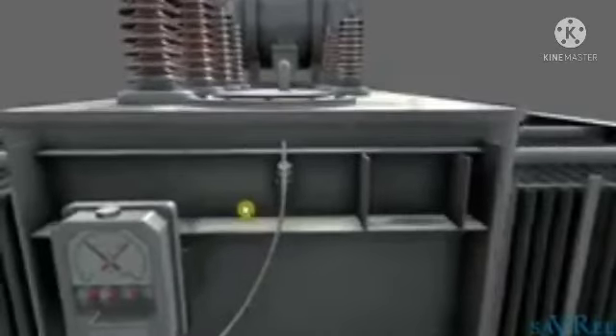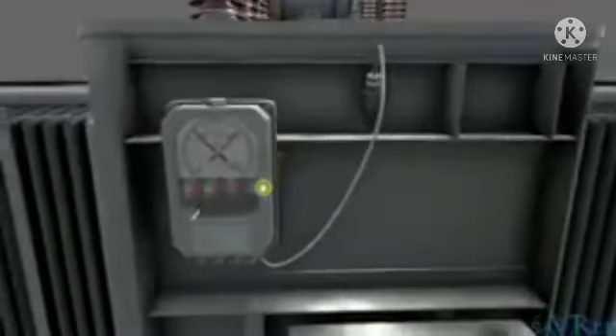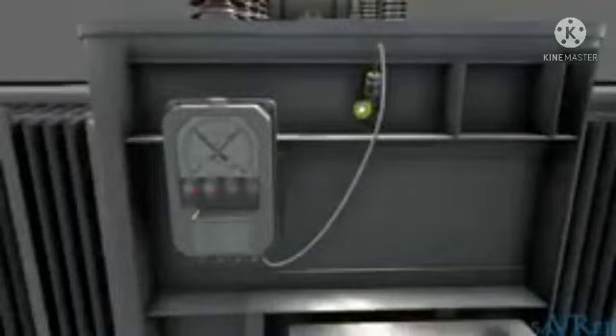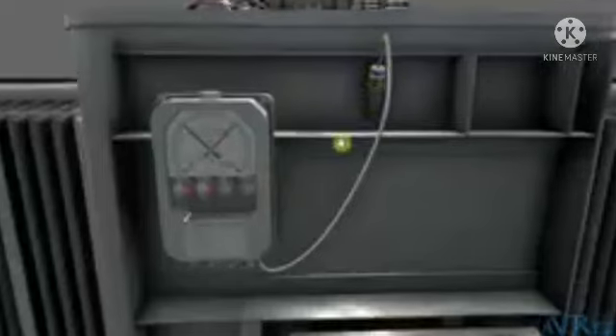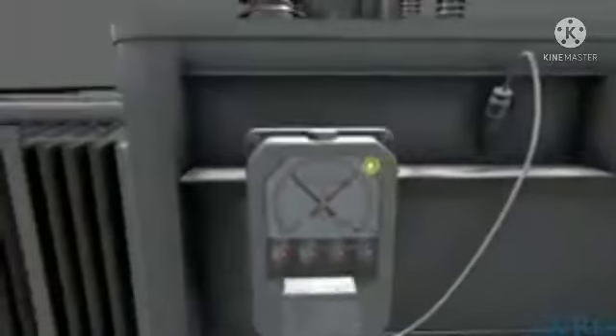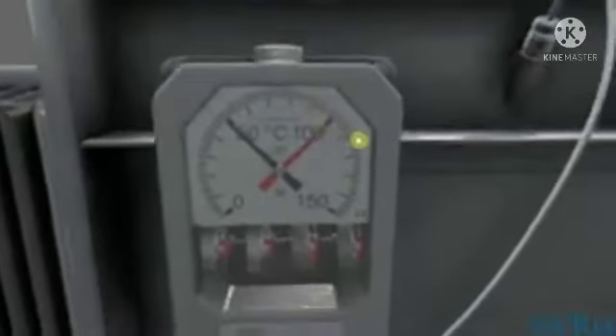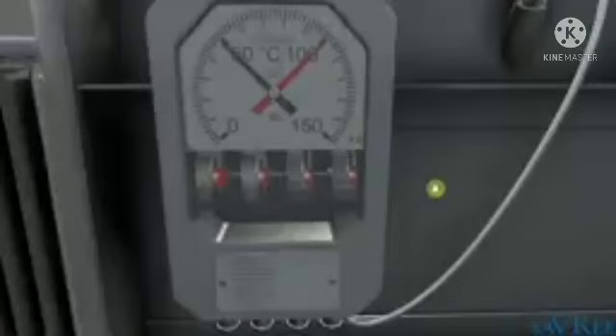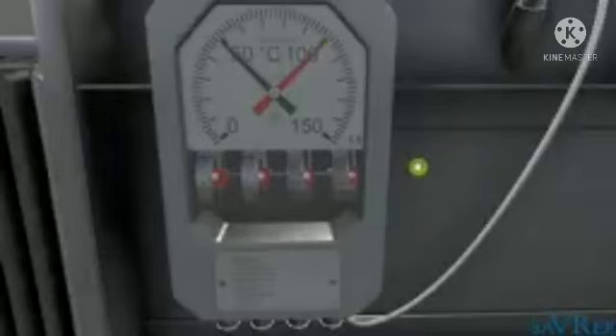If we go this way, we can actually have a look now at the final component, and that is a temperature indicator and temperature thermometer. The thermometer has been mounted within the tank, we can see it here, and the indicator is mounted on the side in order that engineers, as they walk past, can look at the temperature gauge and assess what it is and if we're operating within normal conditions. The red needle itself is used as an alarm set point. If the black needle should come around and surpass the red needle, we're going to get an alarm.